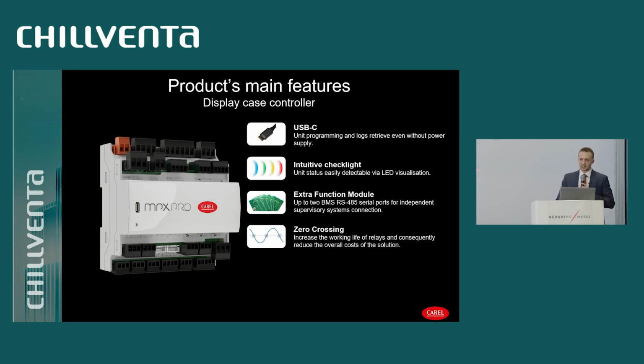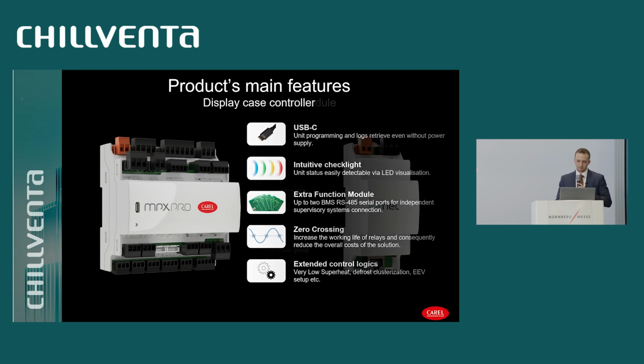Zero crossing functionality. The new platform is equipped with this kind of technology that can detect when the power supply is passing through zero in order to open or close the digital output. In this way, we can extend the lifespan of the digital output because we avoid the in-rush currents. Extended control logics, for sure, starting from the consolidated ones, smooth lines, and so on, but also a very low superheat control mode, defrost clusterization, and a simplification of how to set the parameters of electronic expansion valves.